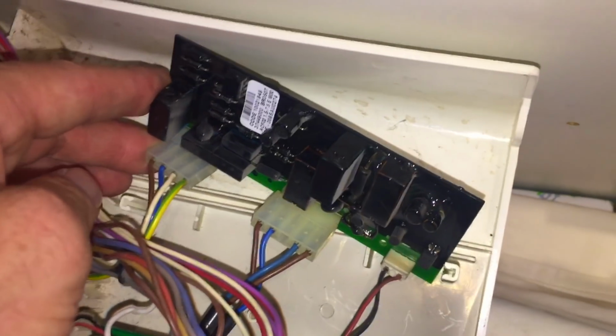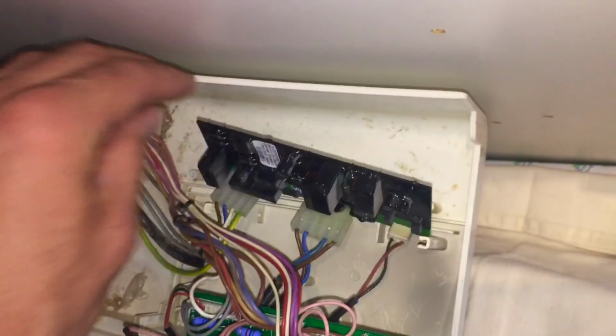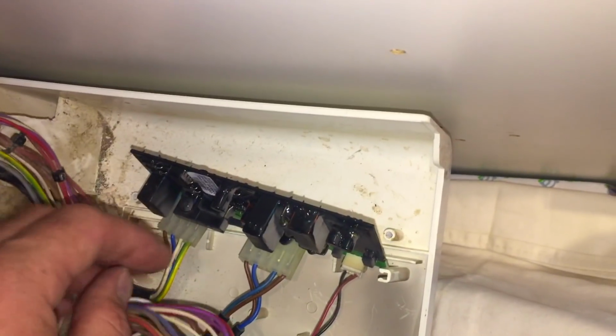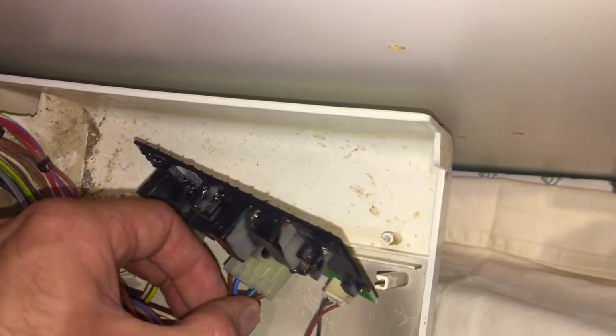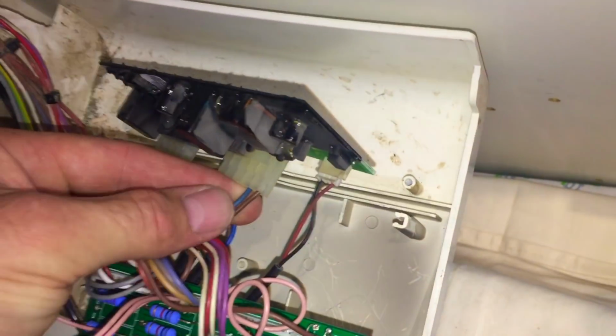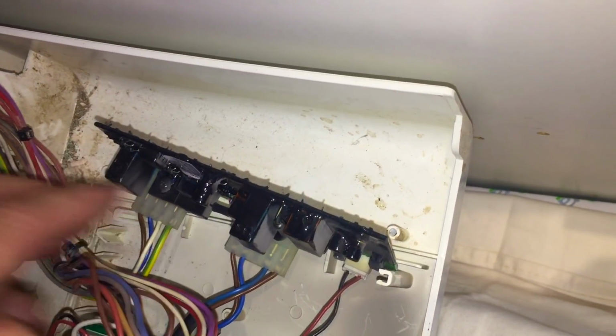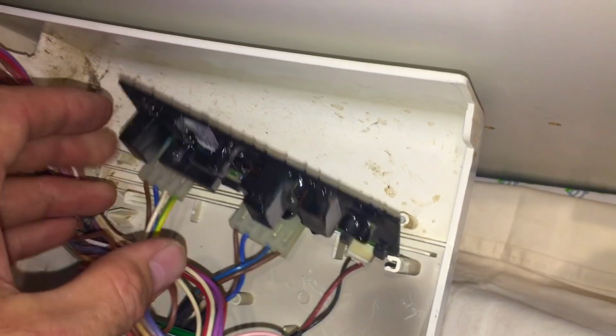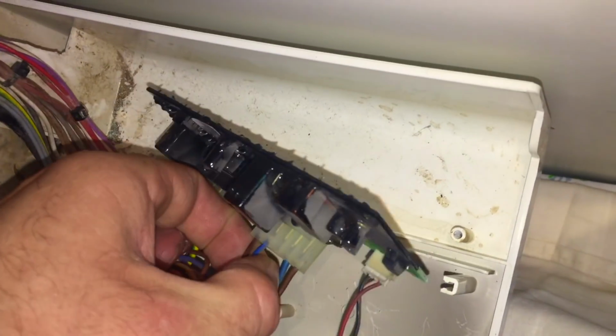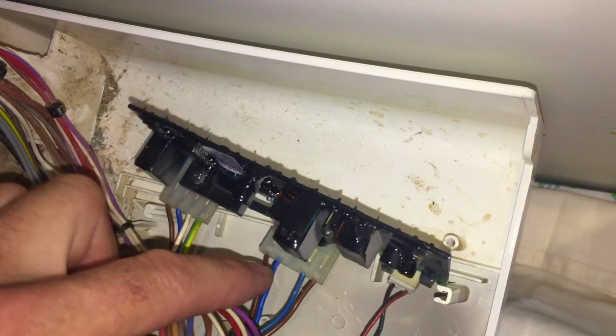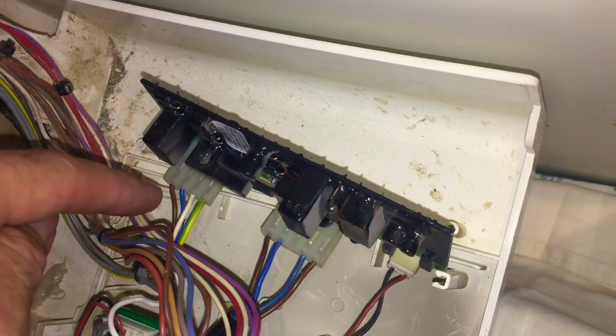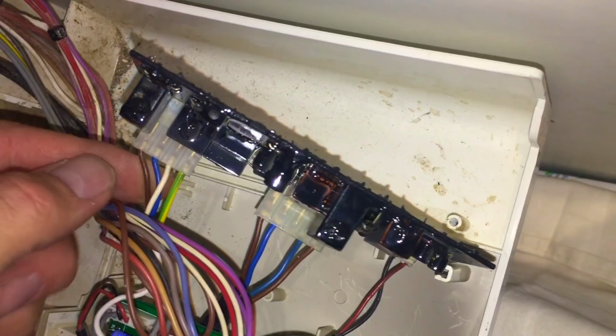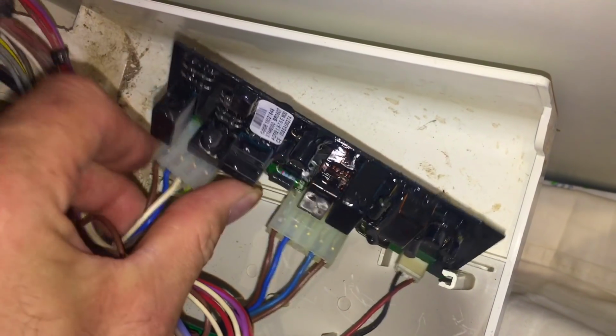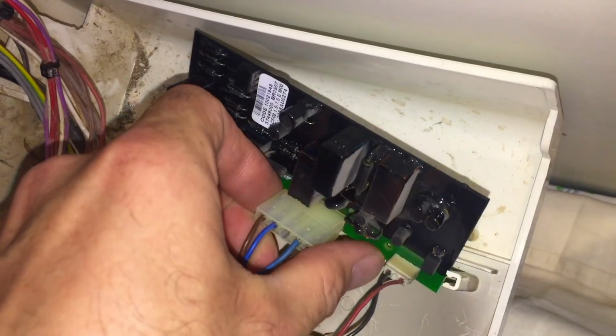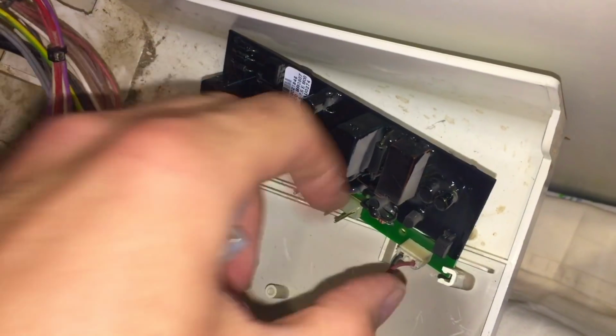So what gave the game away that it was going to be this is because power comes into it here, on these two wires. These two are to open the gas valve, and the rest of this is for spark and rectification. So we had power coming in, the gas valve did open, but we just didn't have spark. So the only thing it can be is anything attached to this plug or this board. We're going to change everything associated with that to hopefully fix this for the customer.